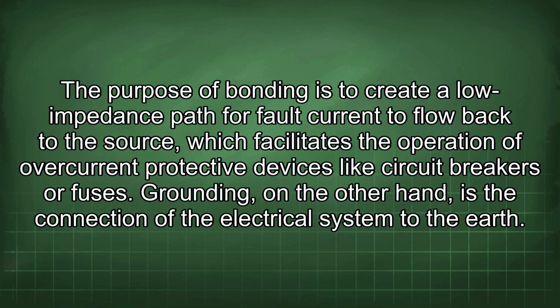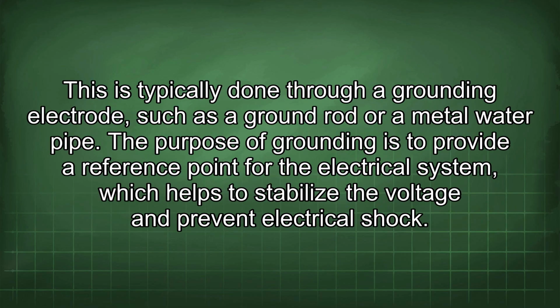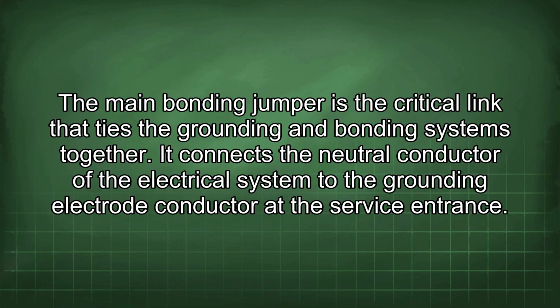Grounding, on the other hand, is the connection of the electrical system to the earth. This is typically done through a grounding electrode, such as a ground rod or metal water pipe. The purpose of grounding is to provide a reference point for the electrical system, which helps to stabilize the voltage and prevent electrical shock. The main bonding jumper is the critical link that ties the grounding and bonding systems together.